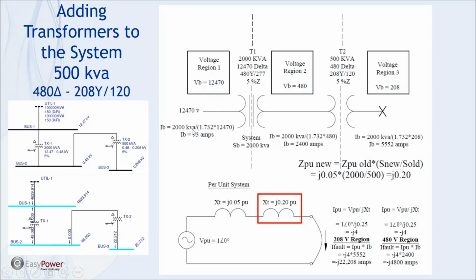And so the further you get away voltage-wise from the incoming service and get into these smaller transformers, your available fault current goes down. And we're not even looking at fuse interrupting characteristics and things like that. Just trying to give a good feel for how the fault current changes as we get to smaller and smaller transformers. And it's because the impedance of this transformer goes way up in comparison to my 2000 kVA. So now in the per unit system, this is just a simple series circuit.